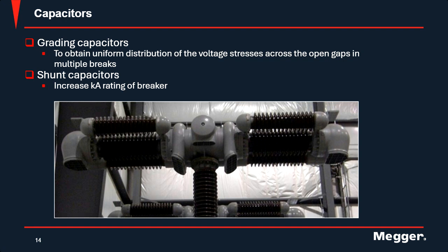Another part of this is that you can have capacitors on your breakers. There are 2 different types of capacitors: grading capacitors and shunt capacitors. Grading capacitors are sometimes used on a circuit breaker with 2 or more interrupters in series. That way you can attain a uniform distribution of the voltage stress across the open gaps. The grading capacitor is connected in parallel with each interrupter unit and has a standard value in the range of a few nanofarads. The shunt capacitors are used to increase the short circuit capabilities of your circuit breaker. In addition to the capacitance increase, they delay the initial transient recovery voltage, and therefore have an impact mainly on the short line fault performance.